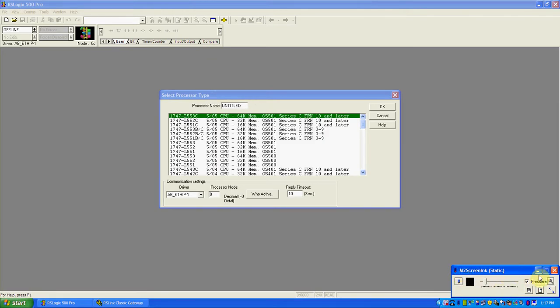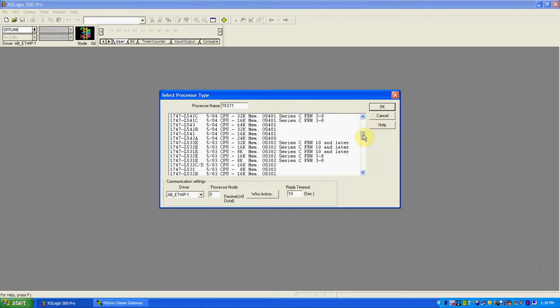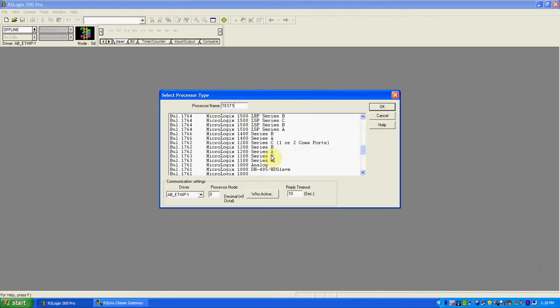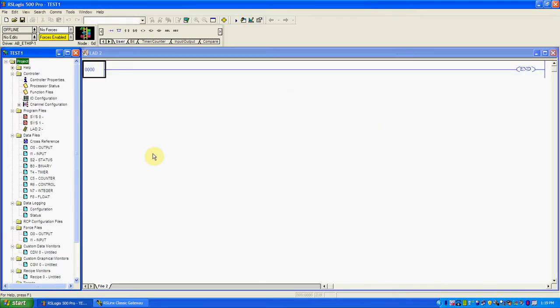I'll show you how we set this up. I'll give it a name — we'll call it test1. All of the stuff we're using in the lab is MicroLogix 1100 Series A, and we're communicating over Ethernet. That's the RJ45 port, that's your CAT5 cable, IP addresses. We'll leave it at Ethernet, but there would be a few different options — every driver installed would show up here. WhoActive is a way that you can choose where you want to talk. You would leave this on Ethernet, say OK, and the software opens up.